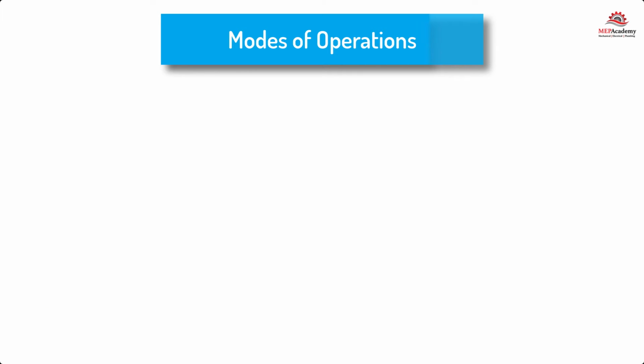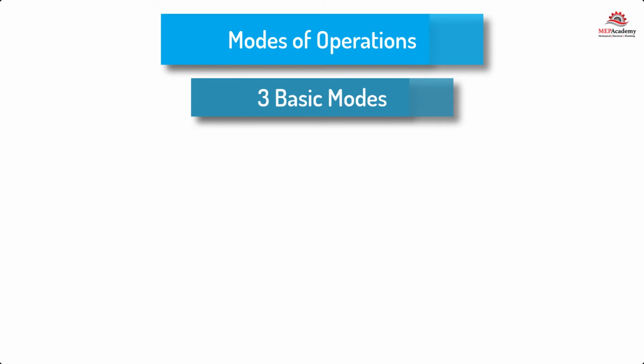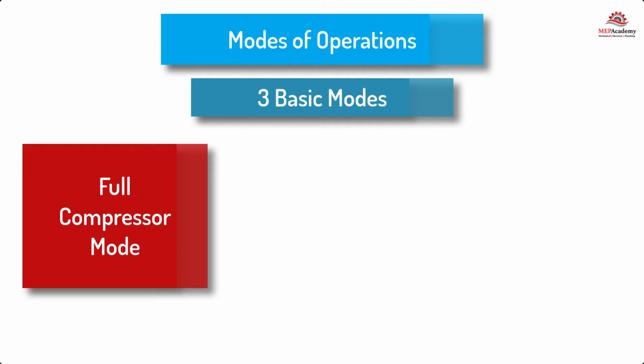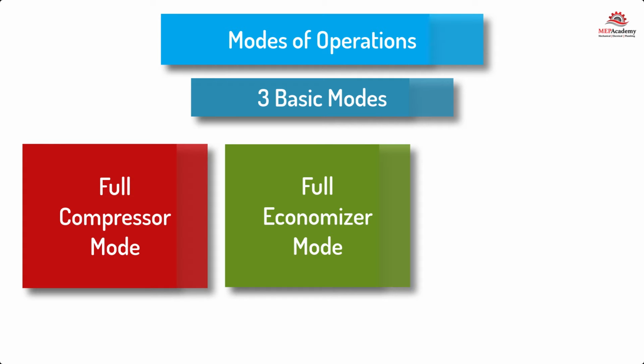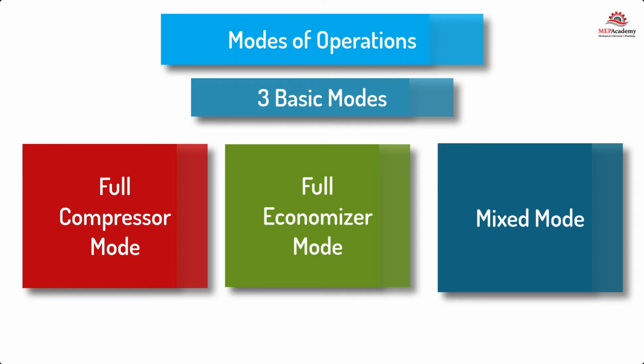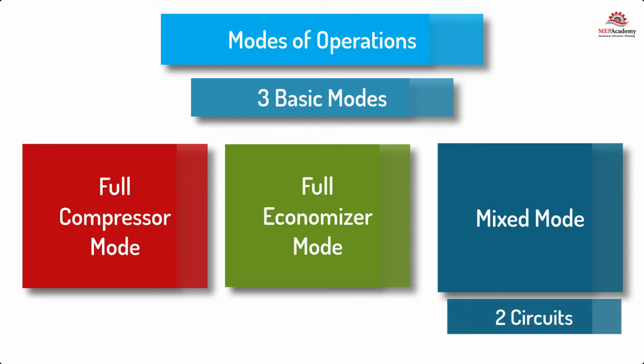Modes of operation. There are 3 basic modes of operation with these units. One is that the data center unit runs in full compressor mode without the use of an economizer. The second mode is to be in full refrigerant pump mode under economizer operation, where the compressors are fully off. And the last method is to use both the compressor and pump in a mixed mode operation. The mixed mode method requires that there are 2 circuits. This allows one circuit to be pumping refrigerant in economizer mode while the other circuit is using a compressor.